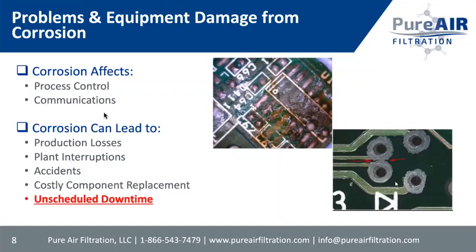Particularly copper is highly corrodable when it comes to sulfuric acid and nitric acid that is generated by SO2, H2S, NO2 combined in the air with normal moisture, H2O. And so it's very easy to corrode the copper. The copper then shorts and the circuit dies, and that whole circuit board is dead and cannot be repaired. Here's an obvious one with all of this brown corrosion, but here's one that's less obvious. These whiskers created in here between the soldering from that corrosion there.